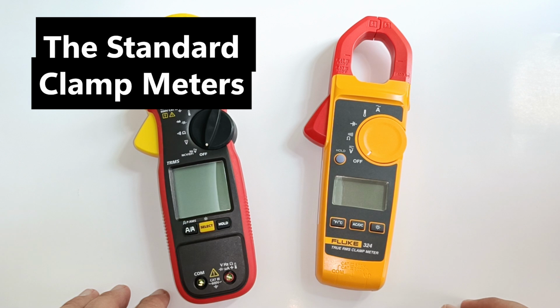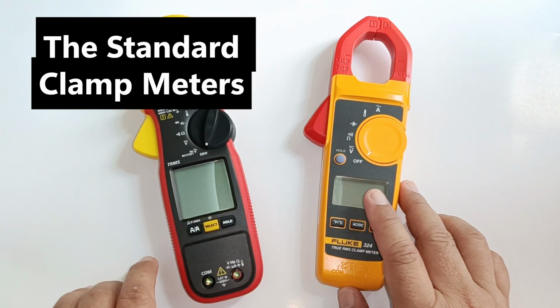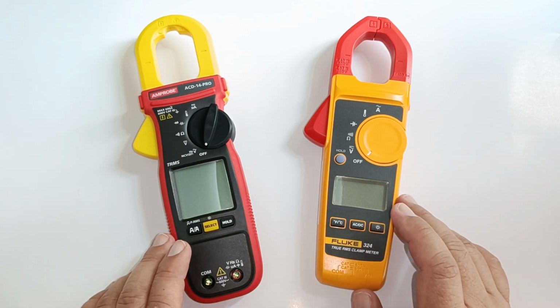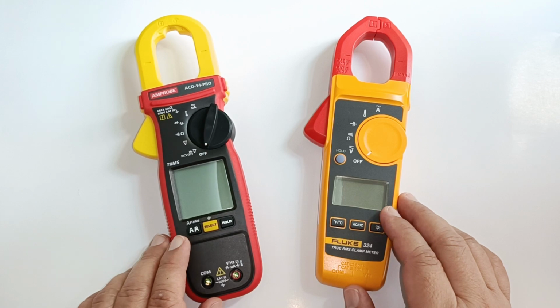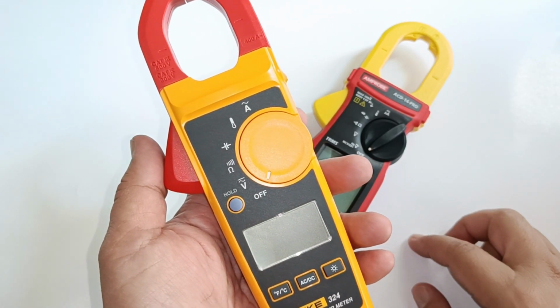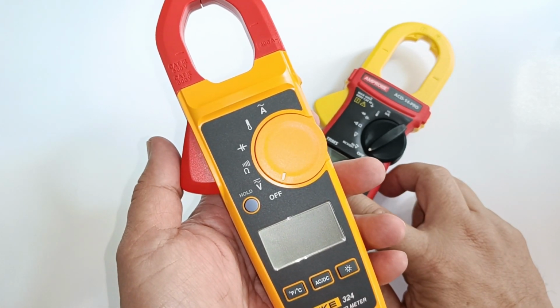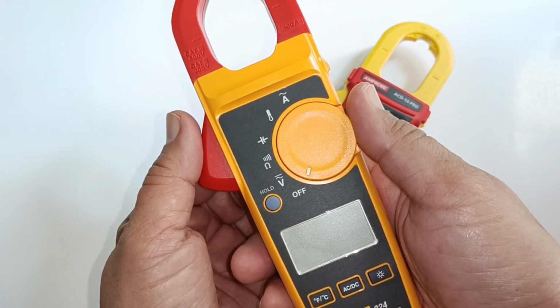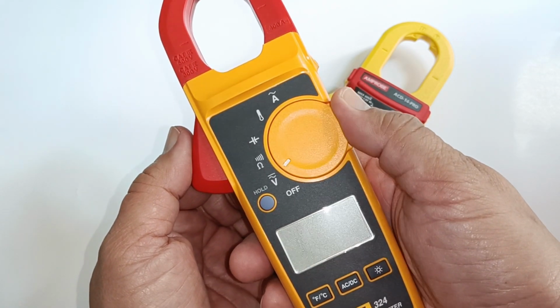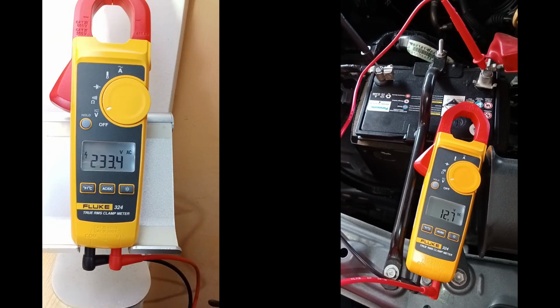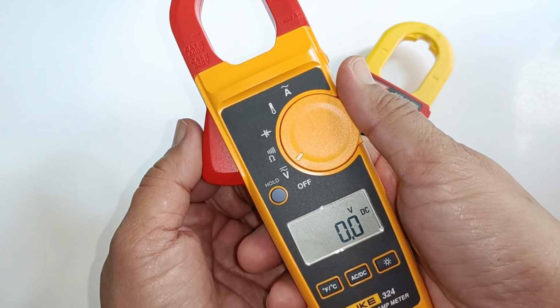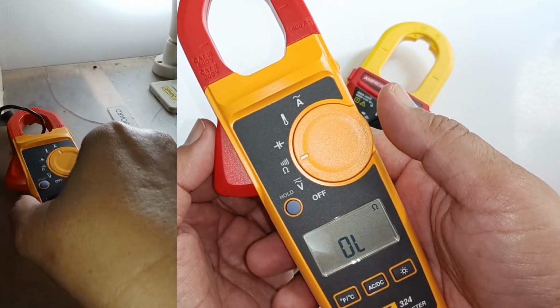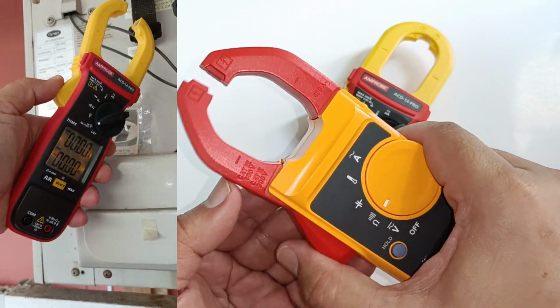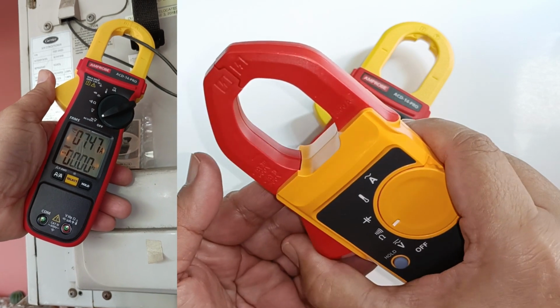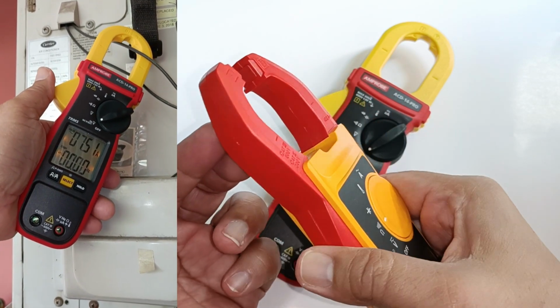Most of you may already be familiar with standard clamp meters like this Fluke 324 and Amprobe ACD-14-PRO. These are just a sampling since you will find many other kinds from different manufacturers. These are excellent test equipment and are staples of electrical practitioners because of their usability in electrical inspections and maintenance. For instance, you can use it like a multimeter to measure AC and DC voltage, resistance and continuity. Its most distinguishing ability is its ability to measure AC current by safely clamping on the conductor to be tested using its jaws or current sensors.